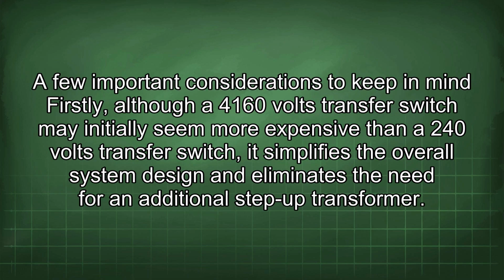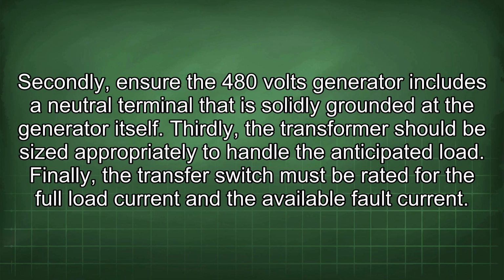A few important considerations to keep in mind. Firstly, although a 4160 volts transfer switch may initially seem more expensive than a 240 volts transfer switch, it simplifies the overall system design and eliminates the need for an additional step-up transformer. Secondly, ensure the 480 volts generator includes a neutral terminal that is solidly grounded at the generator itself. Thirdly, the transformer should be sized appropriately to handle the anticipated load. Finally, the transfer switch must be rated for the full load current and the available fault current.